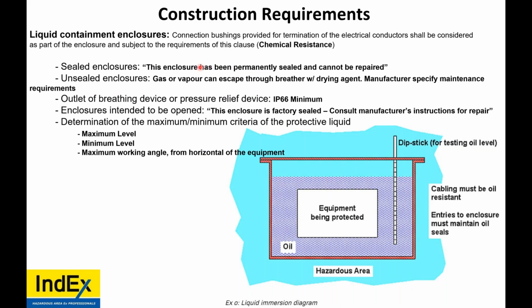So liquid containment enclosures. Connection bushings provided for the termination shall be considered as part of the enclosure and shall be subjected to this clause, meaning it must have chemical resistance. So any of the bushings inside have to be chemically resistant because they are either immersed in oil or above, and they will have oil on them. Now, sealed enclosures need to be permanently sealed and cannot be repaired. They need to be labeled with that.